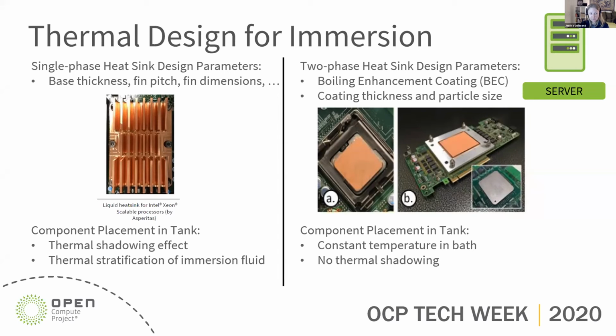As mentioned previously, component placement in the tank is also important. Just like with air, there are thermal shadowing effects in single phase immersion. If there's thermal stratification of the immersion fluid in the tank—cold liquid at the bottom and hotter liquid on top—you want to place components with the most stringent thermal requirements at the bottom.